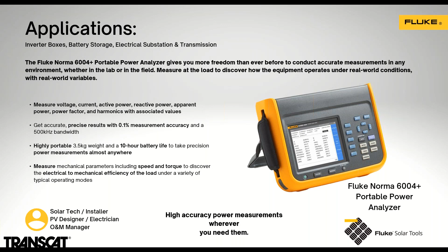A lot of problems happen, not necessarily on the DC side as much as on the AC side, with transients. Any issues on that hard connection to the step-up transformer and out onto the grid could literally be back feeding into that smart inverter, and then from that point tripping out that system. So talking to them, having some type of power analyzer is going to allow them to determine any transients or any issues on that. Let's go to our next one.